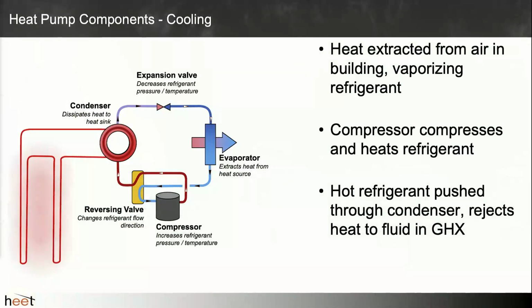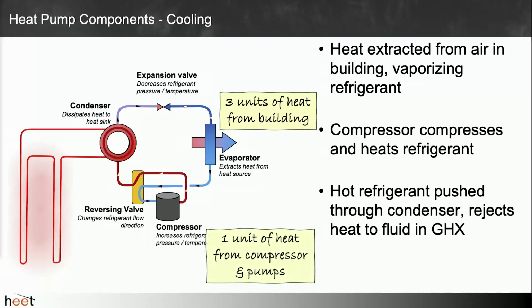In cooling mode, we have our heat that's extracted from the air in the building, vaporizing the refrigerant, so those 3 units of heat from the building. We have our compressor again that compresses and heats the refrigerant. Our reversing valve is on, right? So we flip that flow of refrigerant, so it's going in reverse now. And then that hot refrigerant is pushed through the condenser and rejects heat to that ground heat exchanger. We need to get rid of that electrical energy, and electrical heat, and that heat from the building. And we put that in the ground loop.